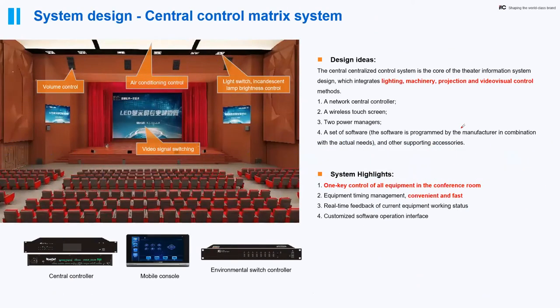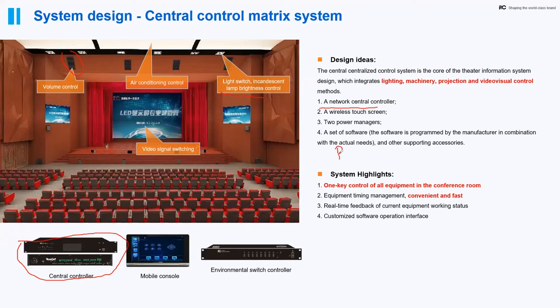We also apply the central control system in the auditorium, because there are numerous devices — sound, air conditioning, lighting, and video signal switching — and all this controlling must be centralized by one device. We apply this centralized center control system: just one network center controller to control all devices, including speaker volume, air conditioning, light switches, video switching for the screen, and third-party device control. As long as the third-party device supports RS-232 or RS-485 protocol, the system can control it.